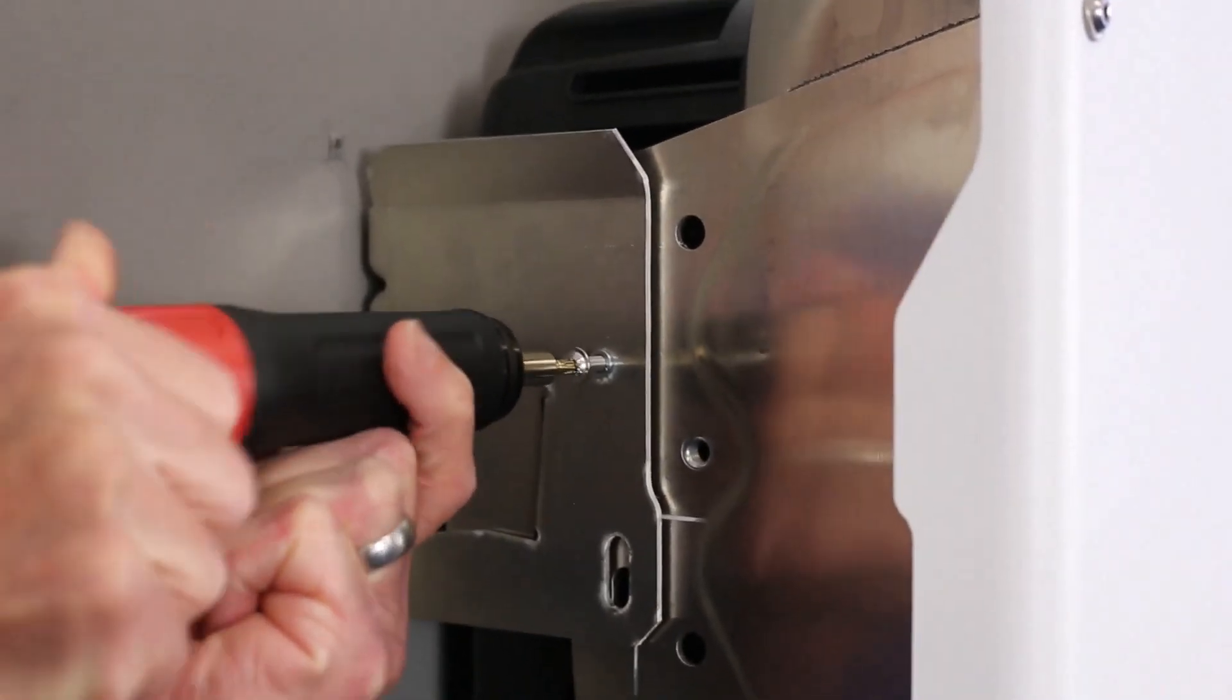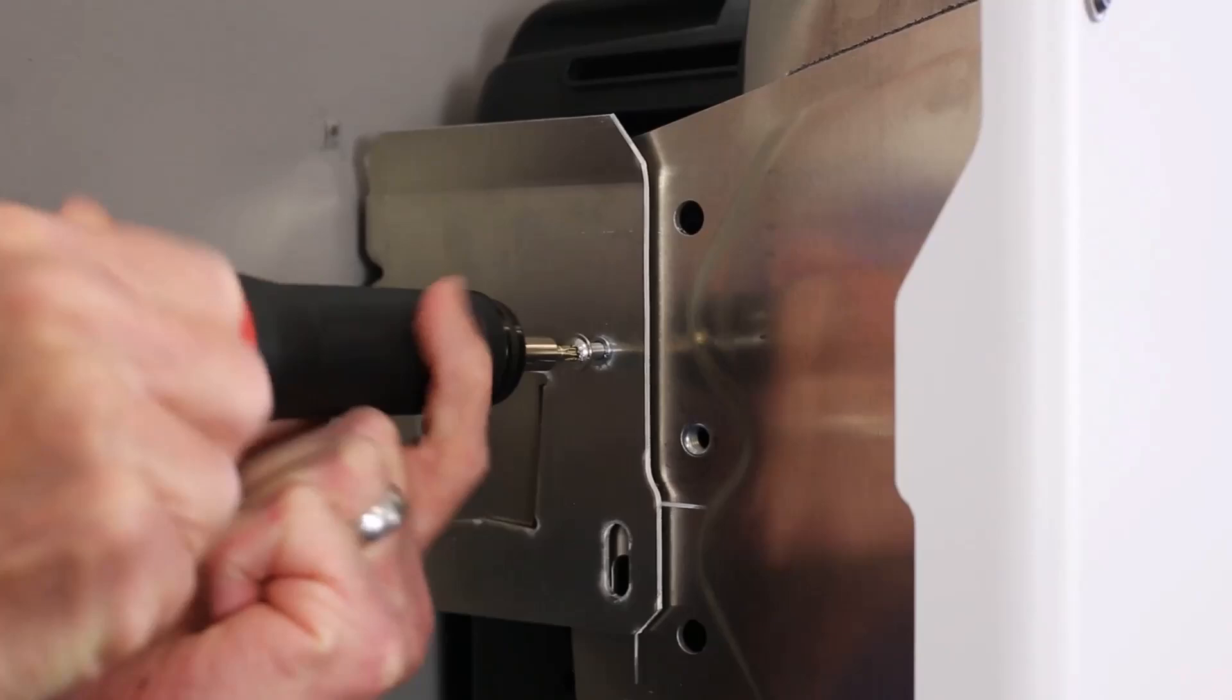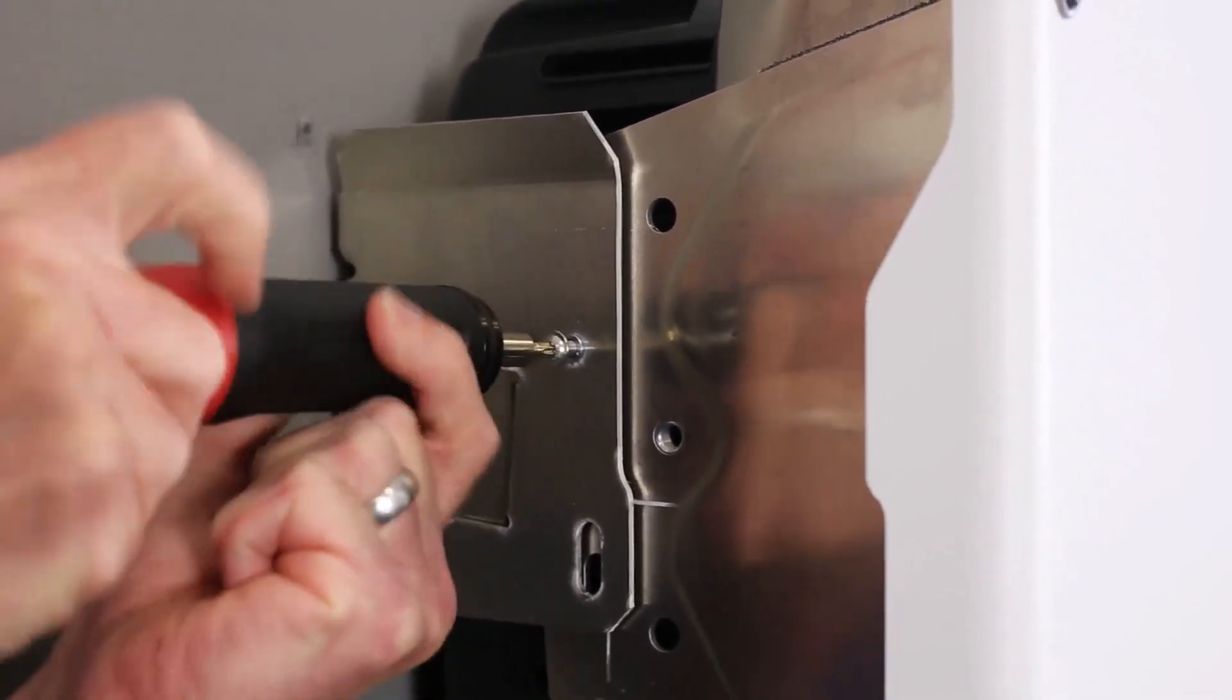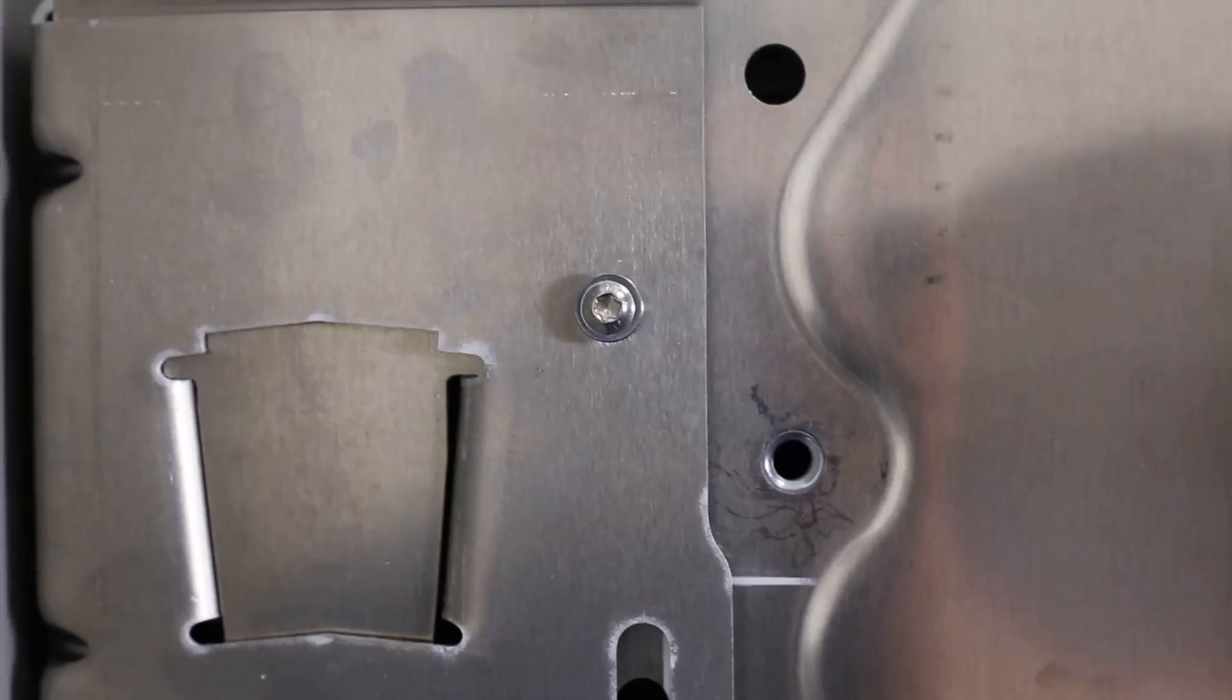Using a torque spec of 13.3 inch pounds, secure the inverter to the bracket using the two included M5 x 14 screws on each side.